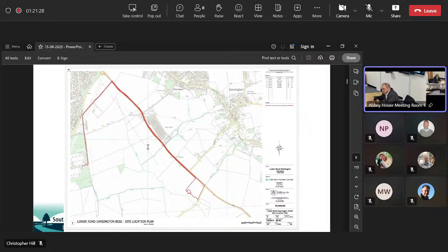The proprietary products available now, which this site would use, the batteries themselves are a self-contained piece of equipment. The embedded technology is within the container itself. So the cooling and the venting and the way that noise is baffled within the construction of the battery casing is all part of the certification that comes with that product. It's delivered to the site as a completed item, not built on the site. So it's already gone through that safety and noise testing before it gets on site. I'm not sure whether I'm comparing apples with apples because I don't know what's at the substation, but certainly in terms of these batteries, there is absolutely no suggestion that there would be any noise problem with any resident or any occupied building within the vicinity of the site.